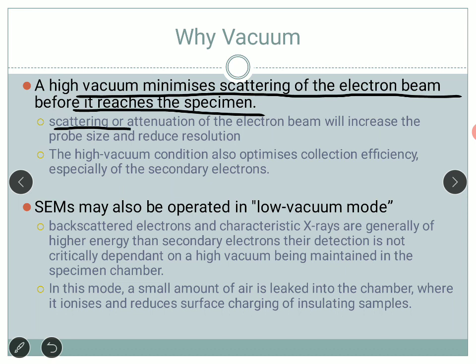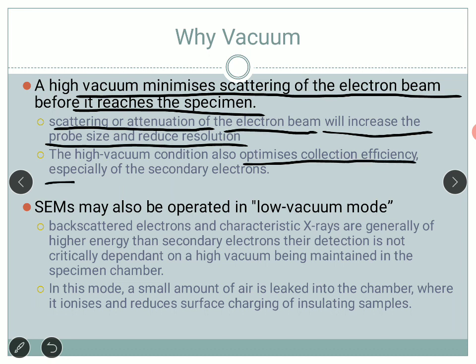Scattering or attenuation — by attenuation we mean the loss of signal of the electron beam generated and incident on the sample — will increase the probe size and reduce resolution. We don't want the electron to get scattered or attenuated, else the probe size increases. We need a very focused beam and higher resolution. The high vacuum condition also optimizes the collection efficiency, especially of the secondary electron. We need vacuum to gather maximum signal.